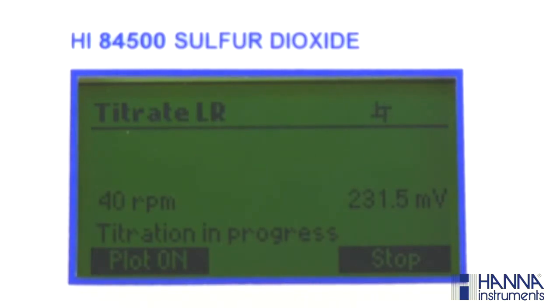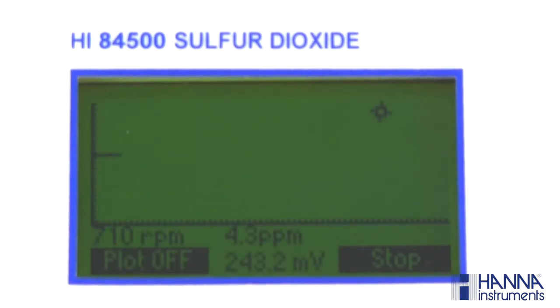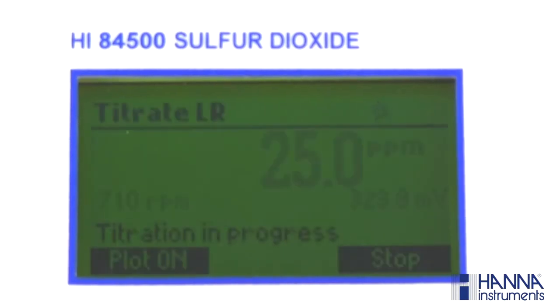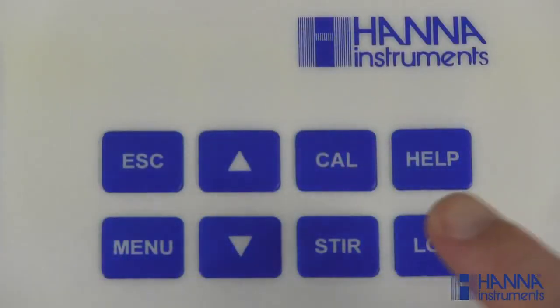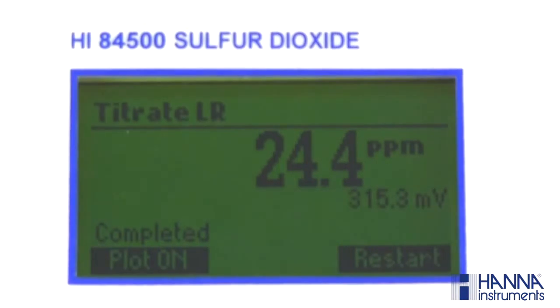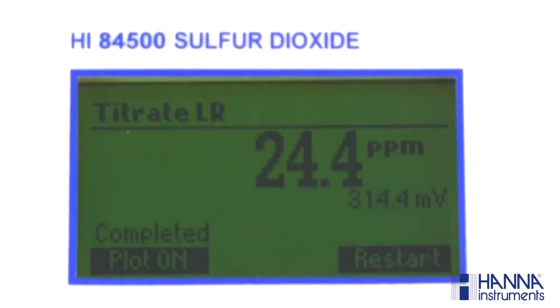The instrument will continuously display the concentration. The titration curve may be seen during measurement by selecting Plot On. You may exit this mode by selecting Plot Off. When complete, the mini titrator will display the concentration of SO2 in parts per million. Press Log if you wish to record the information. The mini titrator is capable of storing up to 200 samples into its memory. Press Restart to begin a new titration, or Escape to return to the menu.